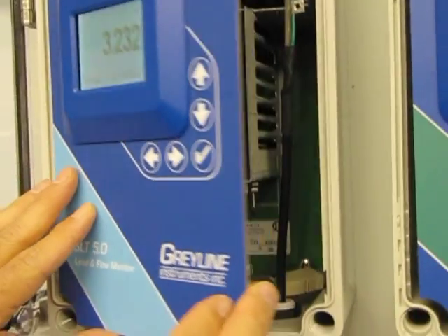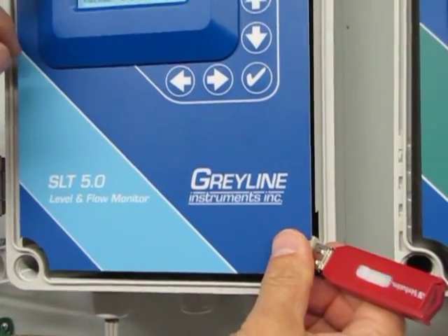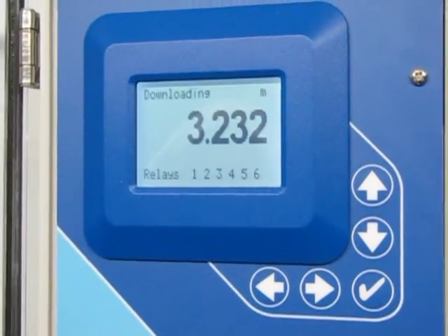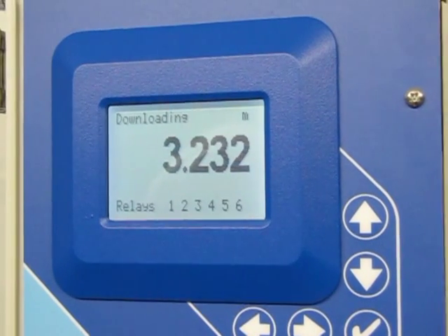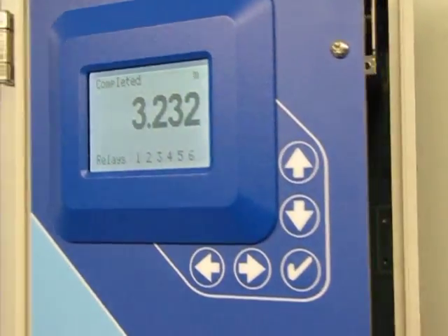After the logger's been running, to retrieve data, we begin by opening the enclosure and plugging any USB flash drive into the USB cable. The download proceeds and the instrument displays 'downloading' as the data is transferred to your flash drive. The time of the download depends on the amount of data that's been stored.